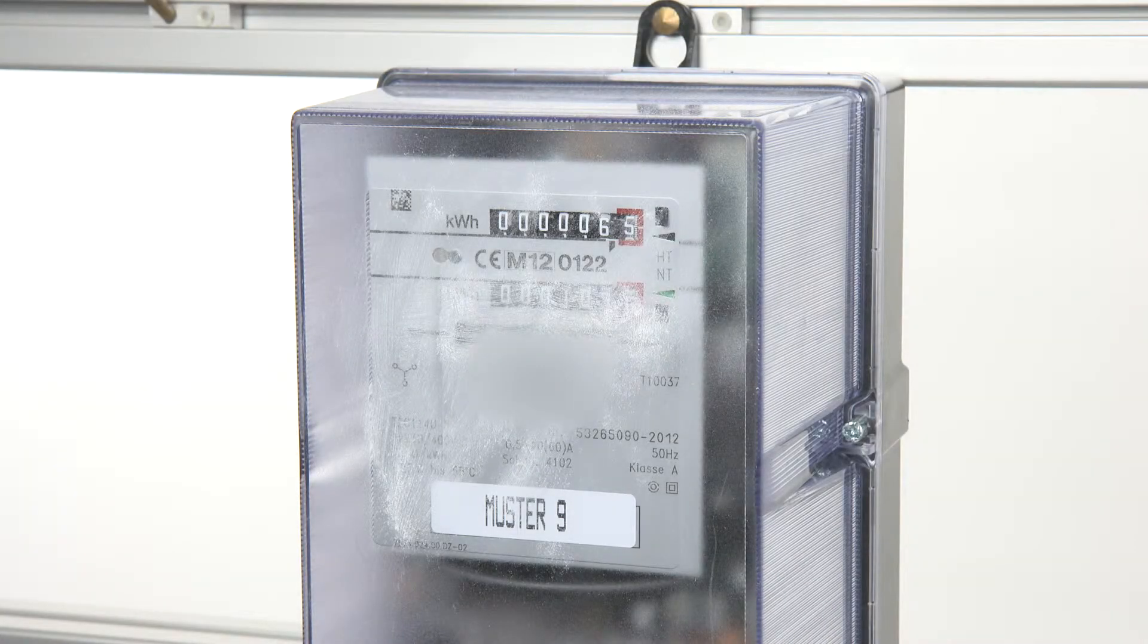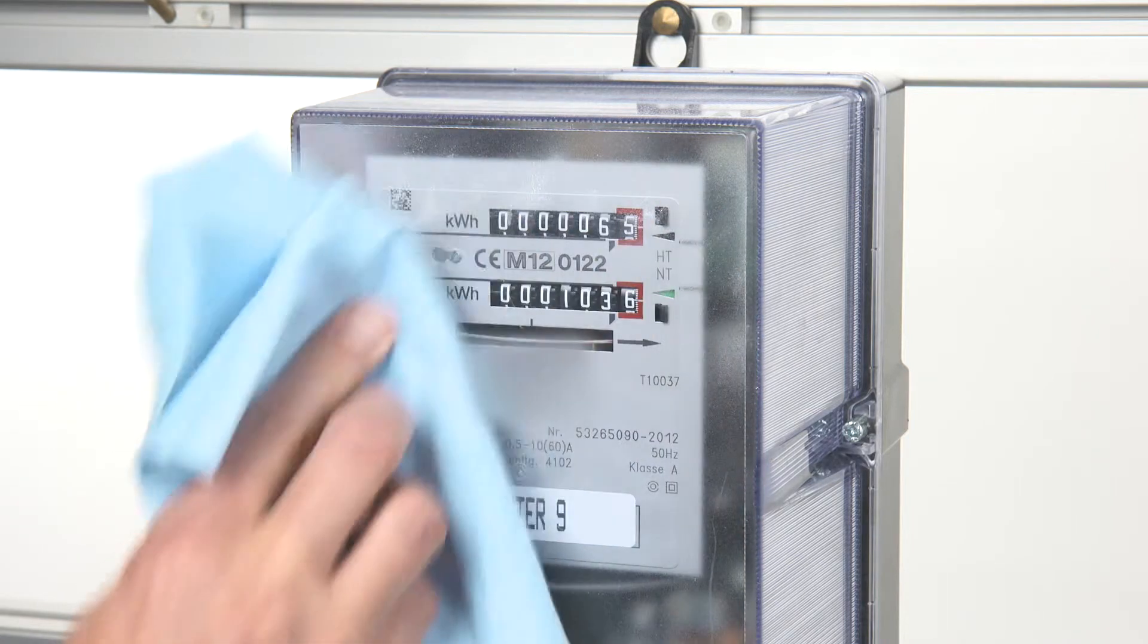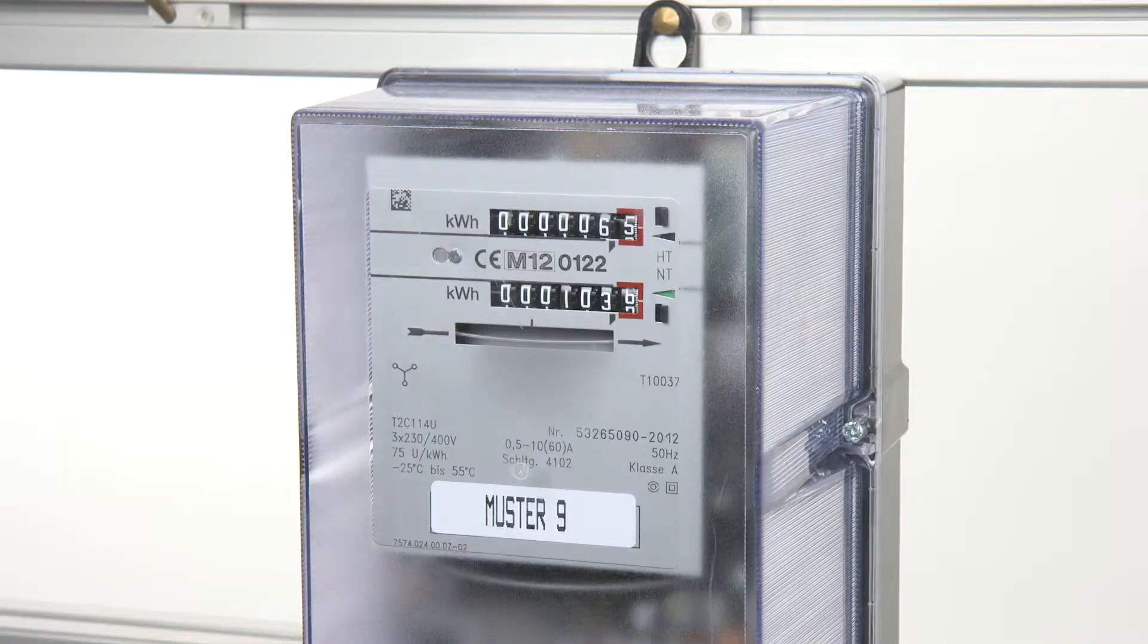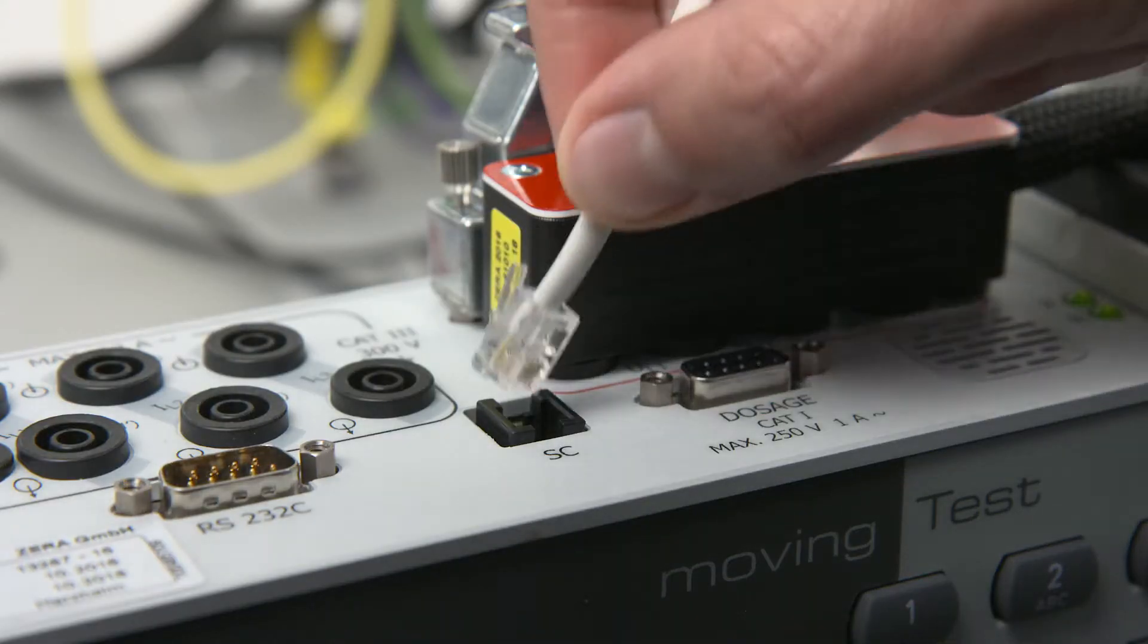To avoid a negative influence during detection of rotor marks of the meter under test, take care that the meter is free from dust and dirt. Connect the scanning head plug with the device.